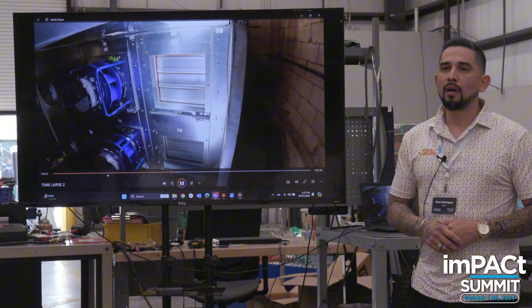As far as parts go, those don't fail too often unless there's an electrical issue. We have replaced contactors, but they're never something that fails just because it's been running for 5-10 years. It's something that fails because there's an electrical surge or something shorts in the system. I don't think it's ever been a thing where they just keep failing and failing.